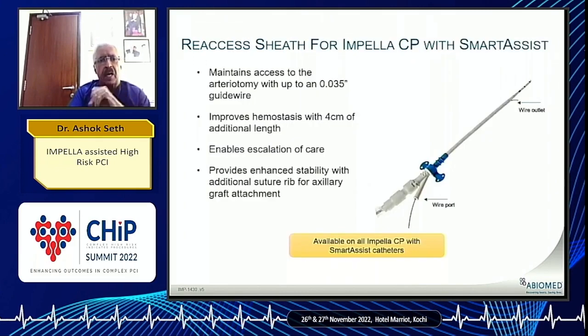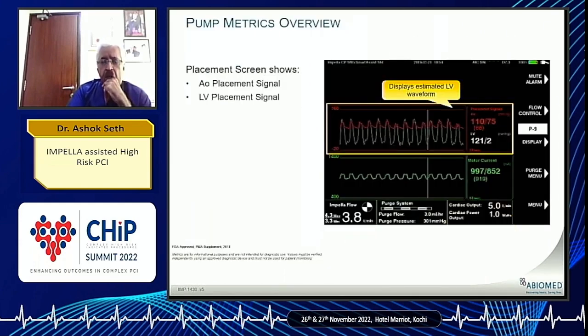There's a wire port which allows you to retain the wire in case of withdrawal of the sheath or IMPELLA, and therefore enables escalation of care if needed, which means if you wanted to go to ECMO, you have a wire there. If you want to de-escalate, if you wanted to put ProGlide, it's still possible. And the screen, of course, gives placement signals, and these signals can be used for subsequent malplacements or replacements in the CCU. So that's a very important aspect of this.